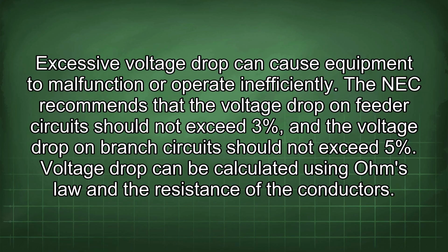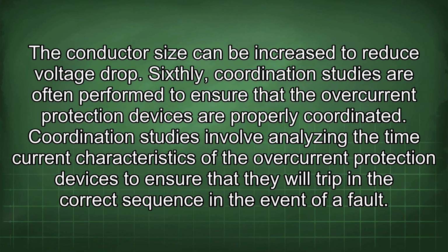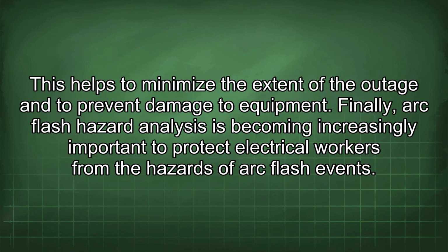Voltage drop can be calculated using Ohm's law and the resistance of the conductors. The conductor size can be increased to reduce voltage drop. Sixthly, coordination studies are often performed to ensure that the overcurrent protection devices are properly coordinated. Coordination studies involve analyzing the time current characteristics of the overcurrent protection devices to ensure that they will trip in the correct sequence in the event of a fault. This helps to minimize the extent of the outage and to prevent damage to equipment.